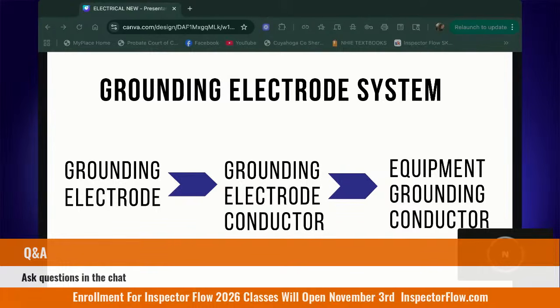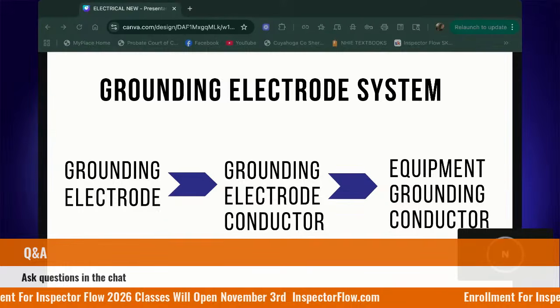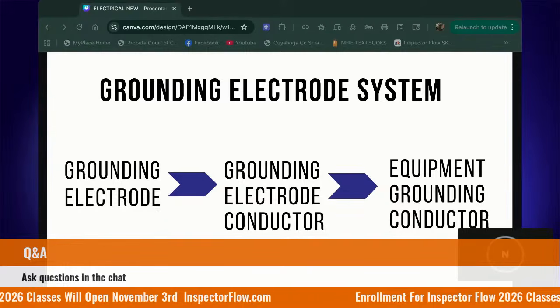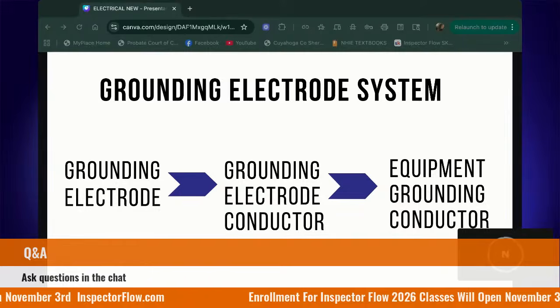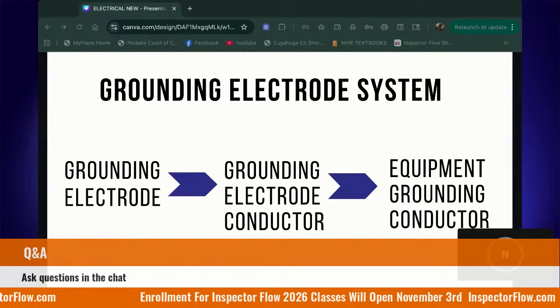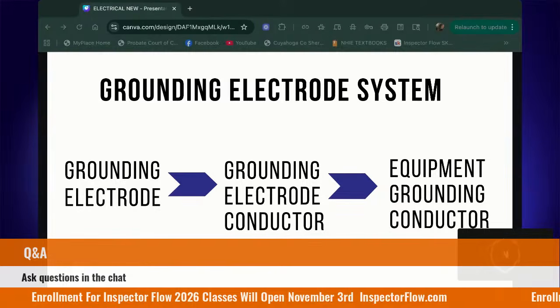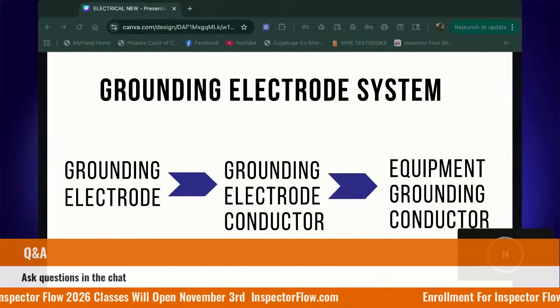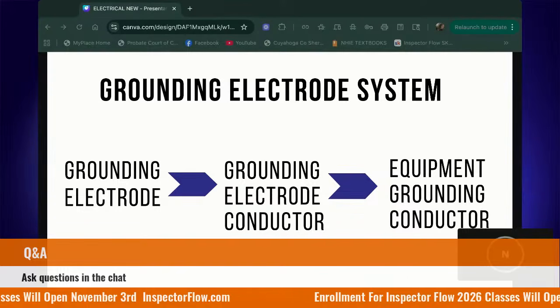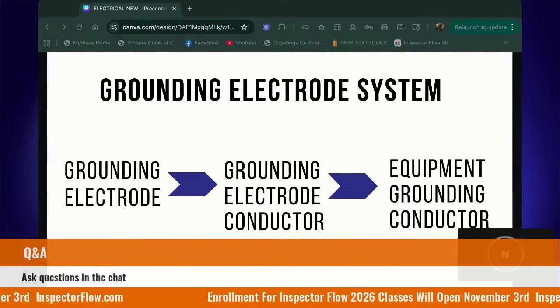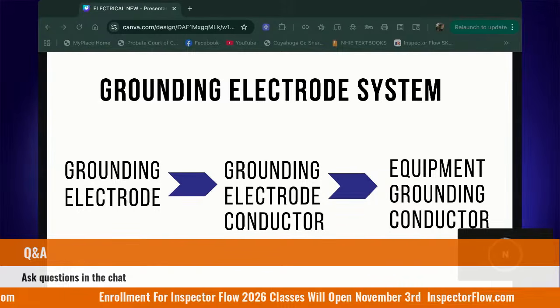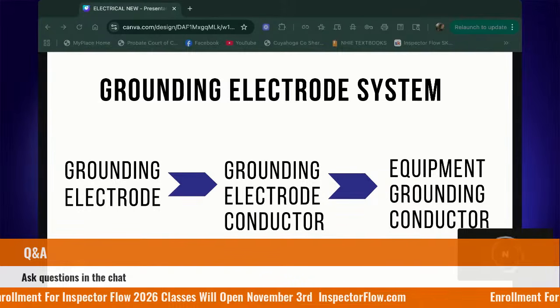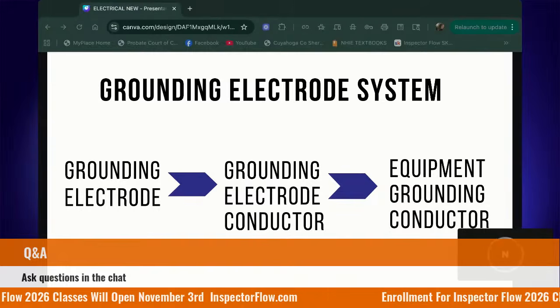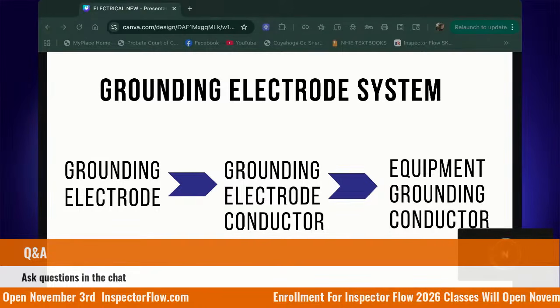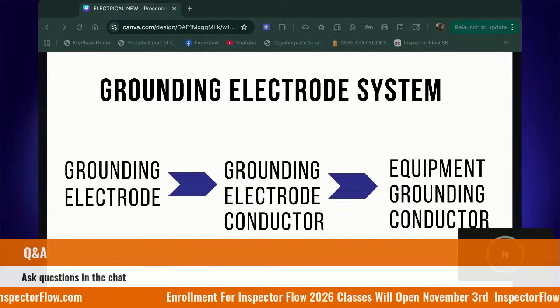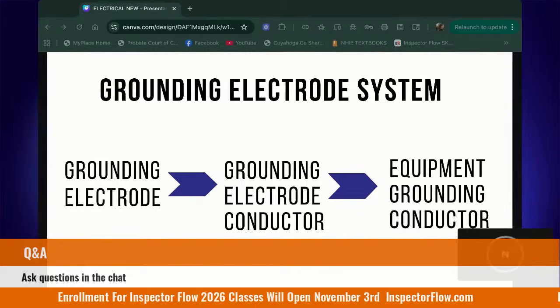So a lot of times you can see the top of it, where there'll be a little loop, and there'll be a copper wire that's connected to that ground rod. Ground rod is the grounding electrode, or the GE. Say that out loud to yourself. The ground rod is the grounding electrode, the GE. It is outside. It is in contact with the ground.